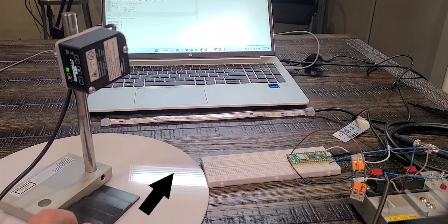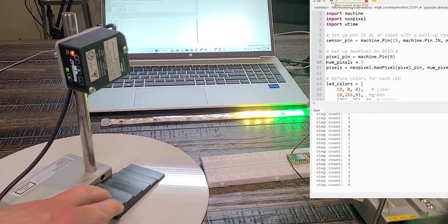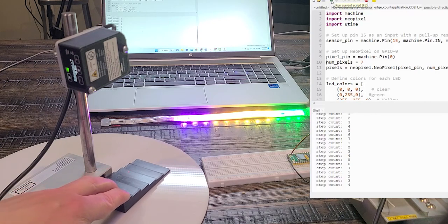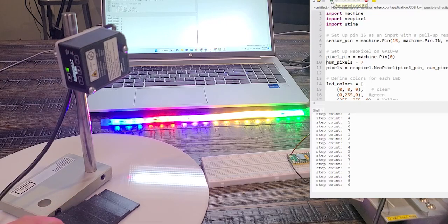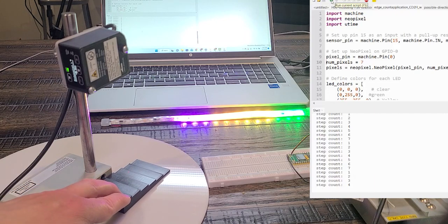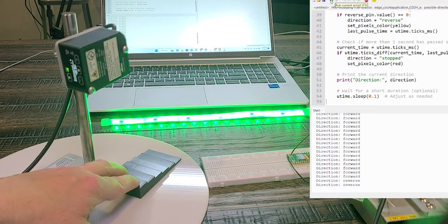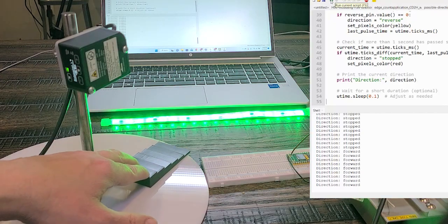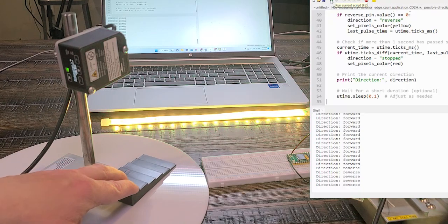The sensor will output in this direction, but not in this direction, at least until it sees a pulse in the opposite direction. You could also set up a second output, so one output is looking for positive edges of 2.5 millimeters and negative edges of the same or different distances, and you could use it to determine if the line has stopped or is moving. If the parts are continuously providing edges in a positive or negative direction, like the stair step, you could do forward and backwards. Although very uncommon, it's interesting to think about the potential of this feature in various applications.